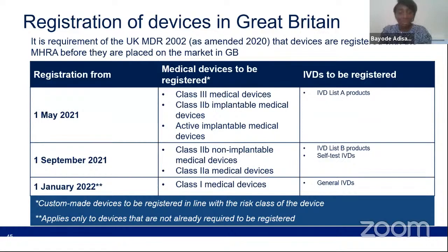The MHRA recognised that this was quite a big shift for manufacturers, so we introduced grace periods for when manufacturers would need to comply. The first deadline was the 1st of May 2021, where it was a legal requirement for manufacturers of Class 3 medical devices, Class 2B implantables and active implantable devices, and also IVD List A products to register their devices with the MHRA. Manufacturers based in the UK can submit this information directly to the MHRA system, but manufacturers not based in the UK need to appoint a UK responsible person to submit this information to us.